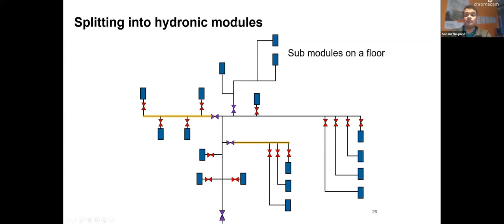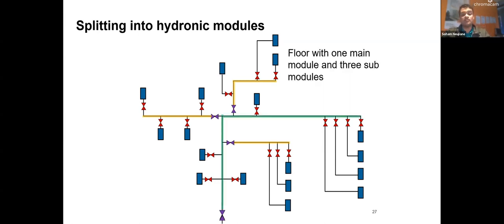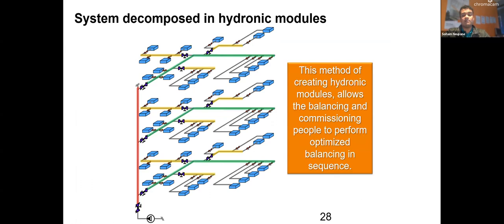And then we go to our third module, same thing: follow the direction of the flow and place a manual balancing valve on each terminal. All right, so what we have now is basically a floor with one main module and three submodules. This method of creating modules is very important because it helps us balance the plant systematically and independently of each other. You can balance in sequence while a part of the project is still being built. You can start balancing the other part and not have to worry about the changes it's going to make to your existing part of the system.